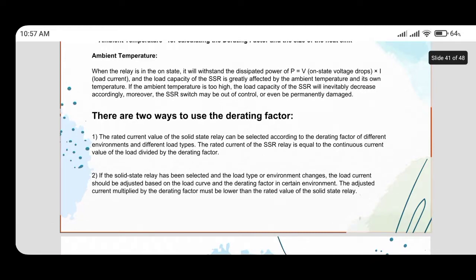There are two ways to use the derating factor. First, the rated current value of the solid state relay can be selected according to the derating factor for different environments and different load types. The rated current of the SSR is equal to the continuous current value of the load divided by the derating factor. Second, if the solid state relay has already been selected and the load type or environment changes, the load current should be adjusted based on the load curve and the derating factor in the certain environment. The adjusted current multiplied by the derating factor must be lower than the rated value of the solid state relay.